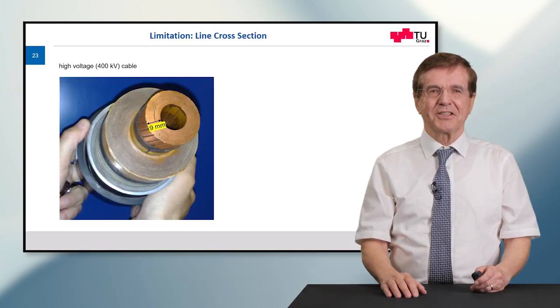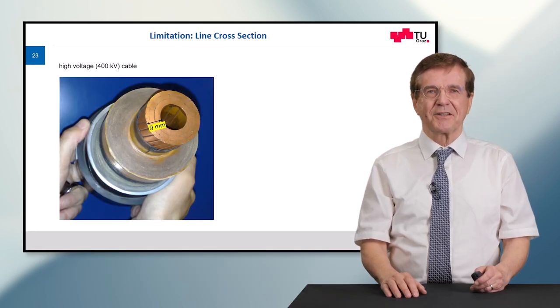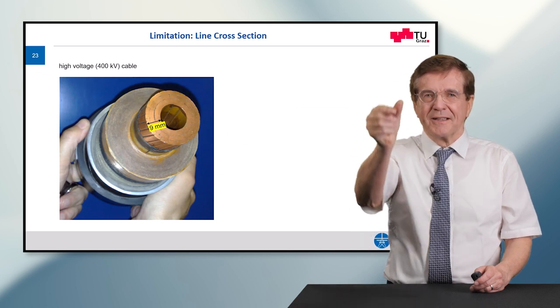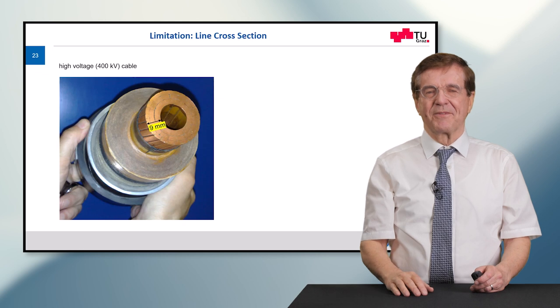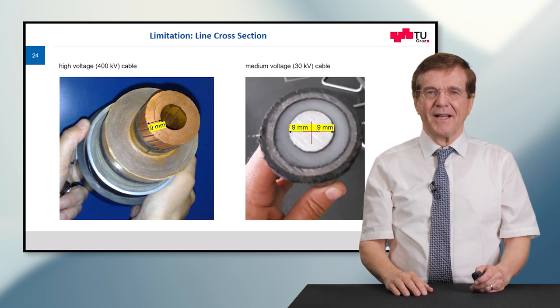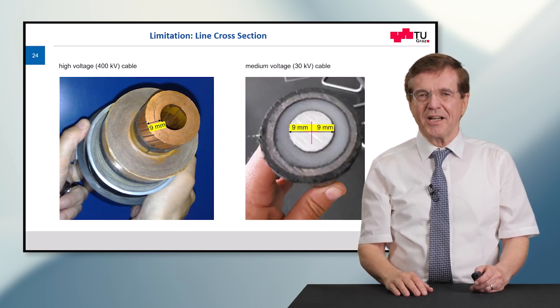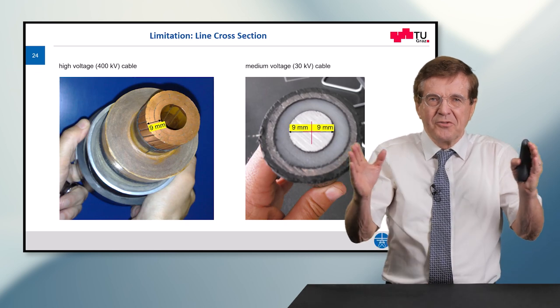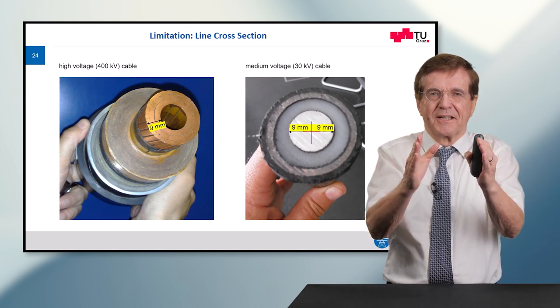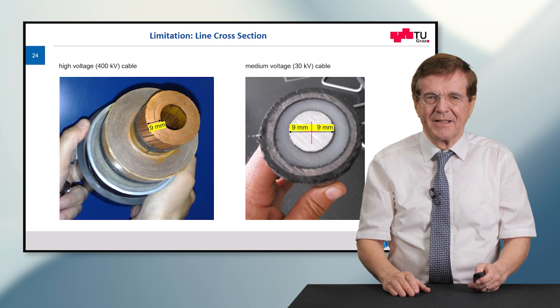Here you can see a typical application for a 400 kV cable. You see the active core of the cable is limited to a thickness of something like nine millimeters. And when we come to a medium voltage cable, we can see these two nine millimeters are compressed together, give a diameter of something like 18 millimeters.